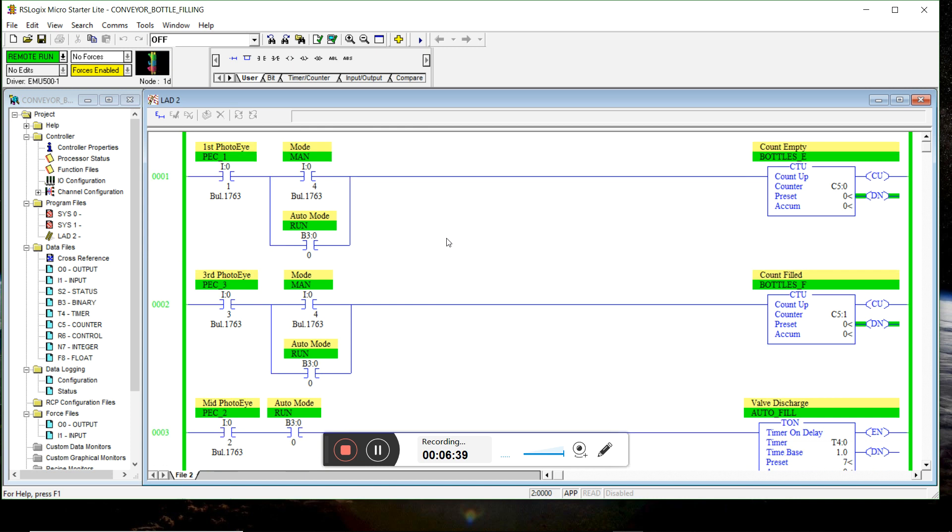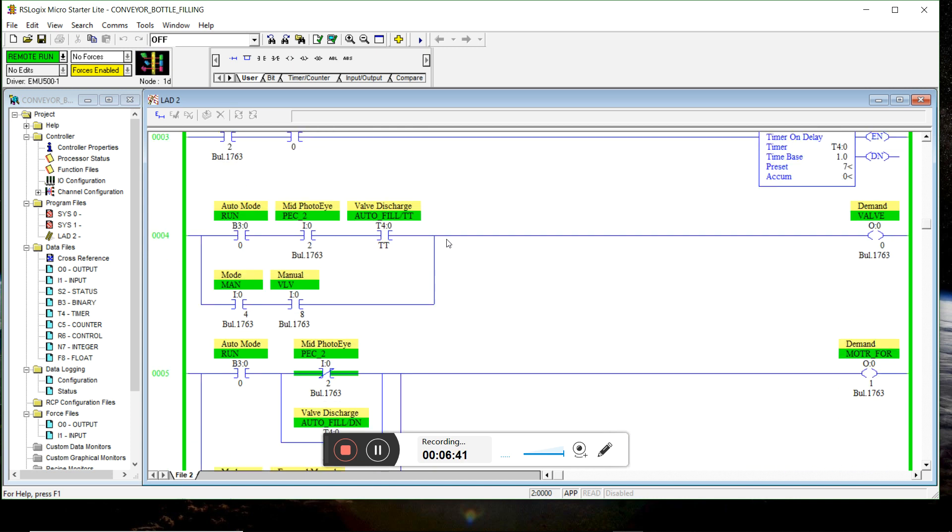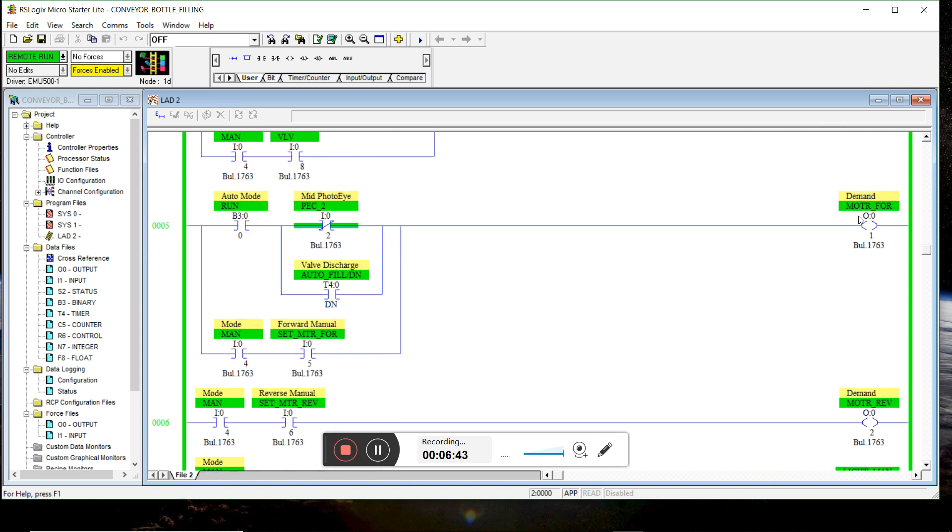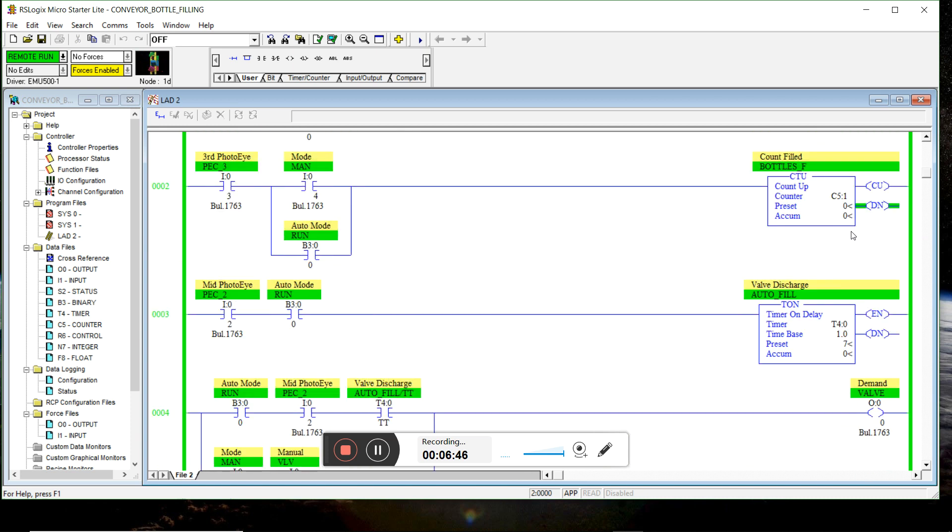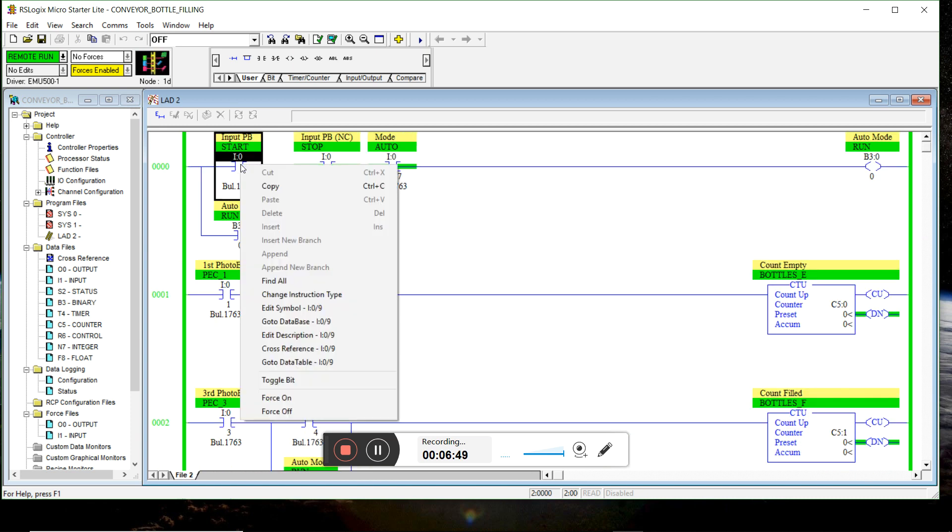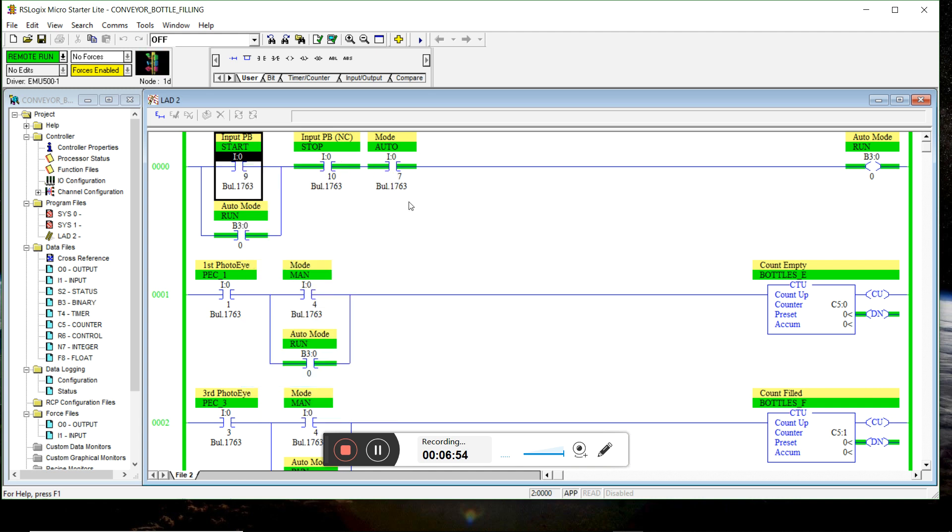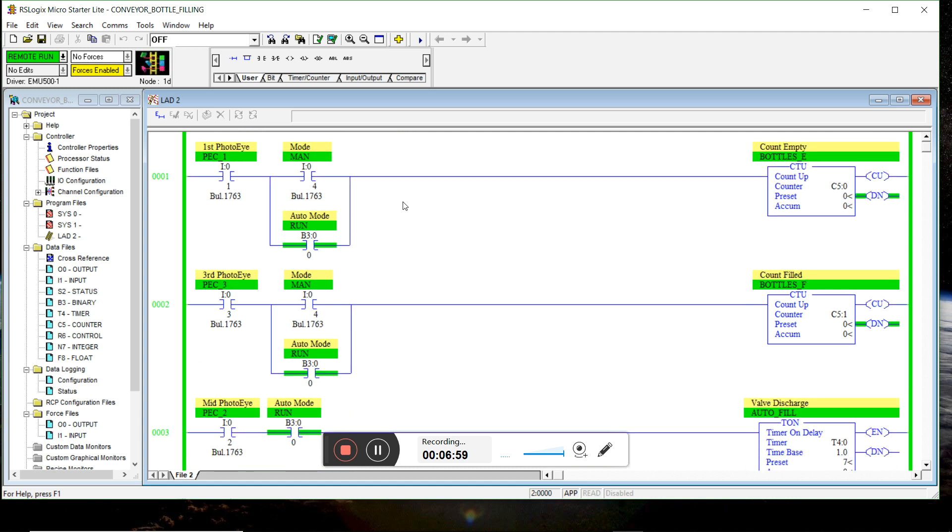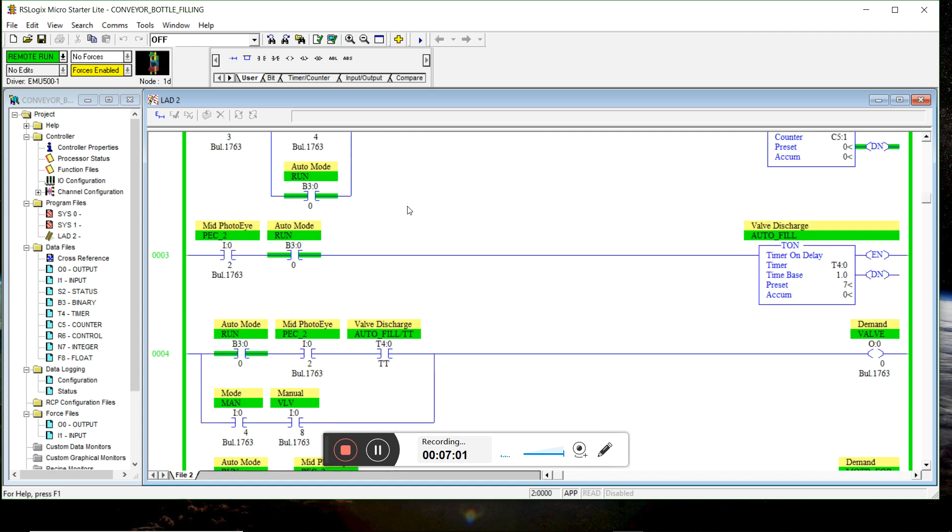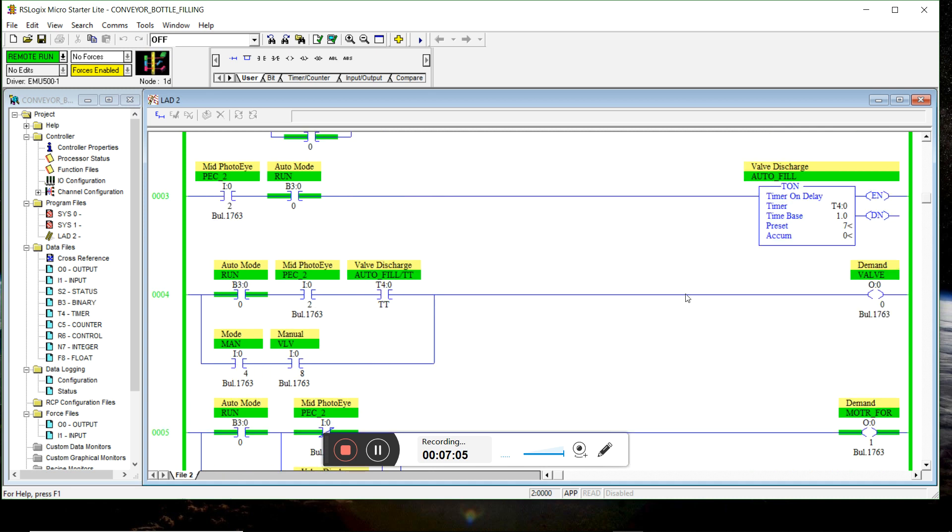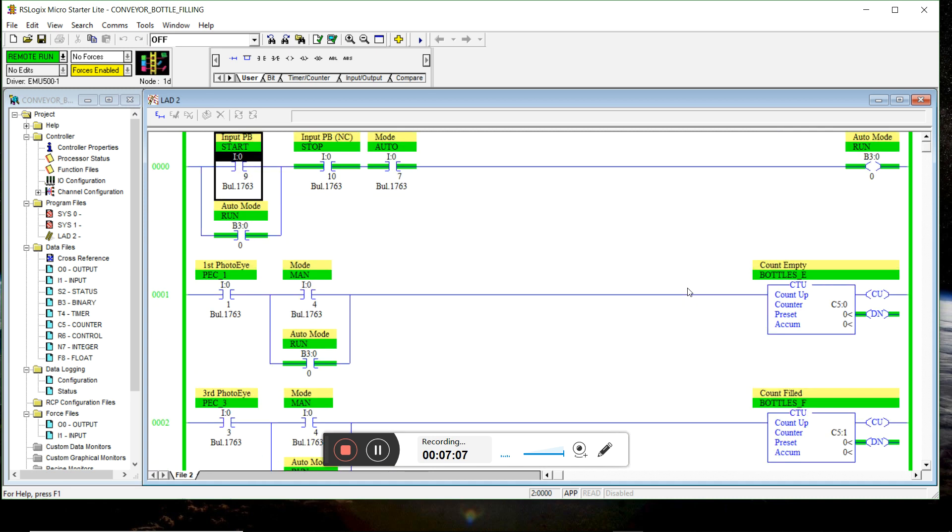So I'm gonna switch to auto mode. And as you can see, my valve's not discharged, my motor's not moving, until I press the momentary push button. And then I let it go. The auto run mode seals. And right now, I'm in auto run mode and motor's moving forward.